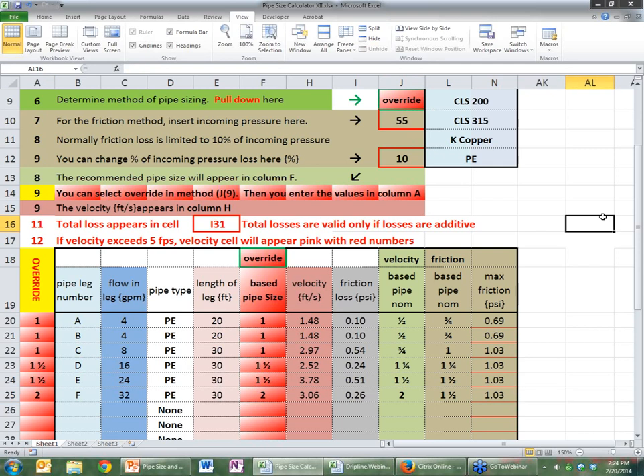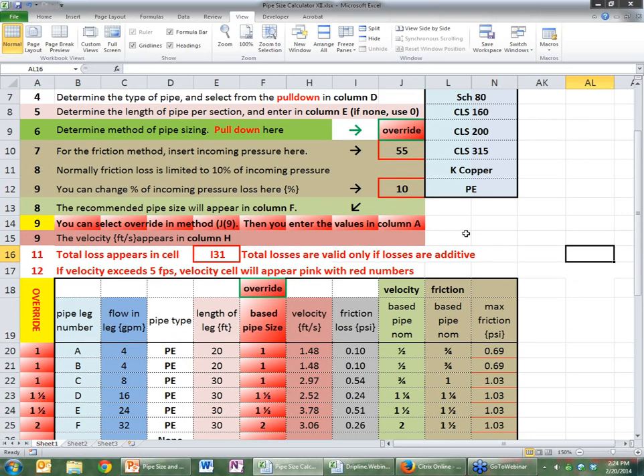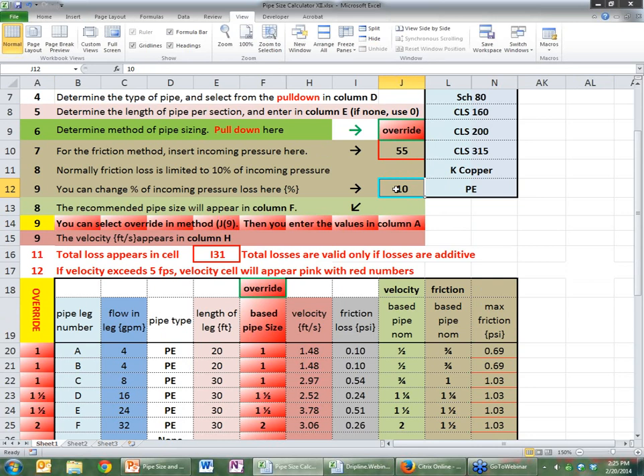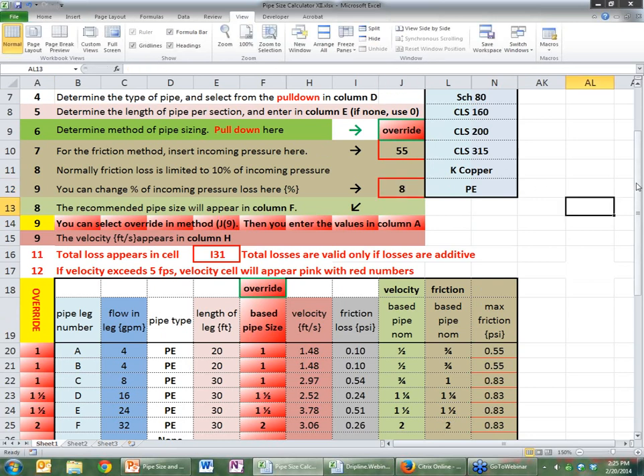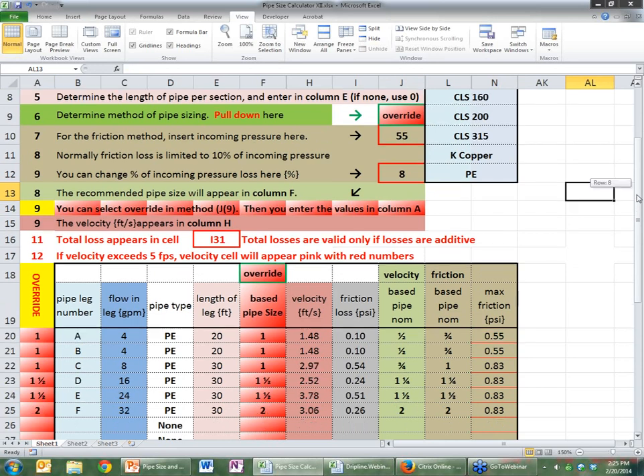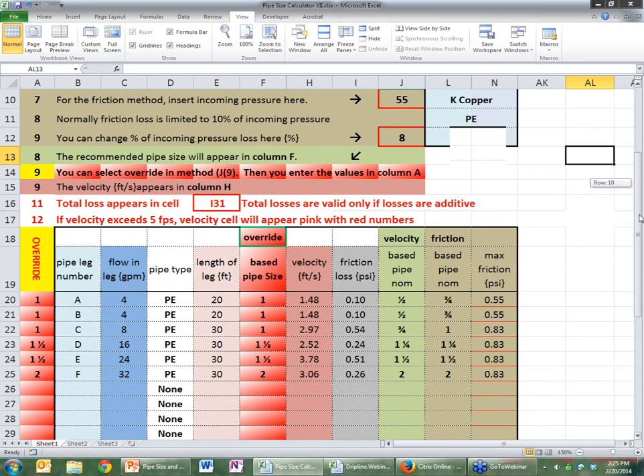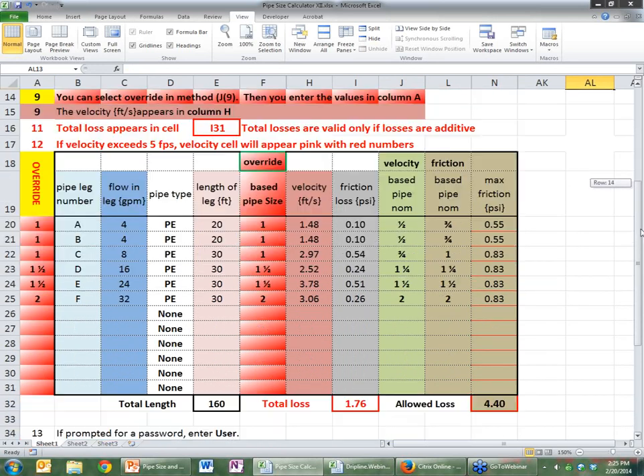Next question. What if the terrain is not level? Now, I haven't taken that into consideration with regard. And the question is, if the terrain's not level, then that impacts the pressure at some distant point. And I haven't built that into this. This is assuming that it's all level. One of the ways you can get around it is to calculate what fraction of your pressure that consists of and then reduce this percentage. So if it's, let's say you're going uphill from your source and you figure that amounts to five feet, that's about two PSI, so maybe that's two percent. And you can make that eight and go from there.